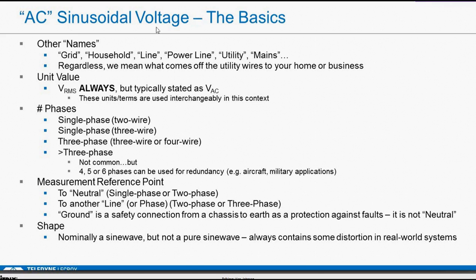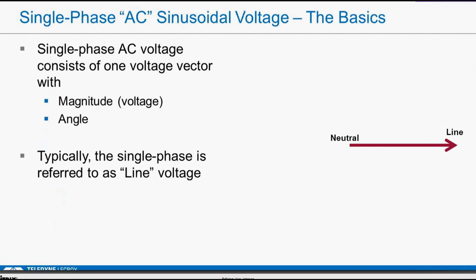When you're measuring voltage, the reference point for voltage can either be to a neutral for single phase or two phase, three wire right here, or it can be to another line for multi-phase, like a three-phase application. Ground is a safety connection from a chassis to earth. It's not the same as neutral, so we always refer to it as line to neutral when we're talking about a reference point. And the shape of a line voltage should be nominally a sine wave. It's never a pure sine wave, but it's very close. There are some rules and regulations that require it to maintain a minimum level of distortion as delivered.